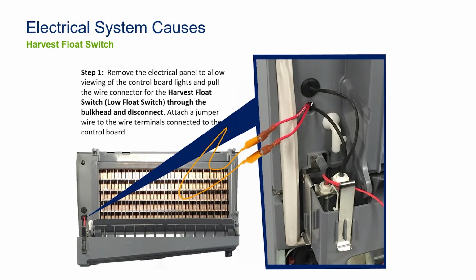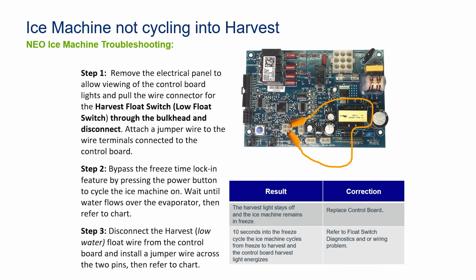At this point, again, when the ball is down, it's a closed circuit. So what we're going to do is put a jumper wire across the wires that track back to the control board. You're going to unplug the float from the harness and then put a jumper on both sides of those red wires there to create a closed circuit. Bypass your 6-minute lock-in freeze. By the way, we have a 6-minute lock-in freeze. We've been doing that for a long time.